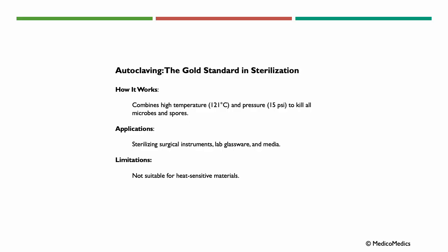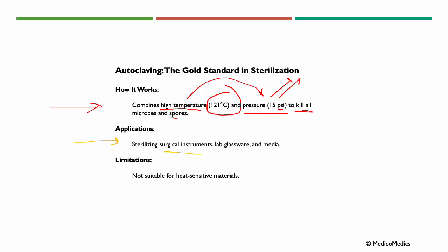An autoclave is like a super-powered pressure cooker, used in hospitals and labs to make tools completely germ-free. It's fast, effective, and very reliable. It works by combining high temperature — 121 degrees Celsius — and pressure of 15 pounds per square inch (psi), using this combination to kill all microbes and spores. Applications include sterilizing surgical instruments and lab glassware. Limitation: it is not suitable for heat-sensitive materials.